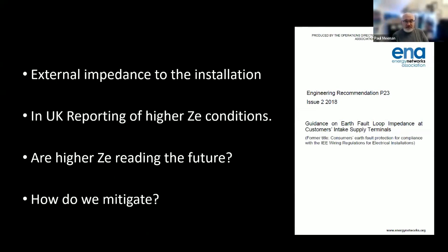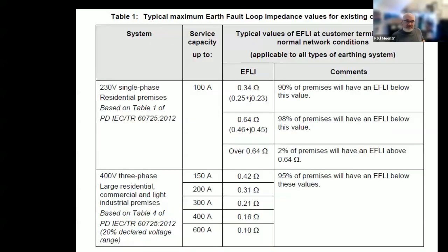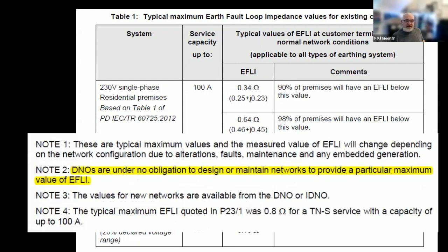Well, naturally, with age, if we're not maintaining stuff, then yes. So how do we mitigate that? Well, you saw in the photos I was putting in discs or rods. There's some really good guidance out there as well, where, in England, we have a 100 amp service head, and it gives you the earth fault loop impedance, and it tells you that 90% will have below 0.34, but they also acknowledge there will be installations, millions of services, where they may be higher than that. And it's good that they're publishing this sort of stuff, because obviously we need these ZEs to make sure we've got sufficient fault current to flow.